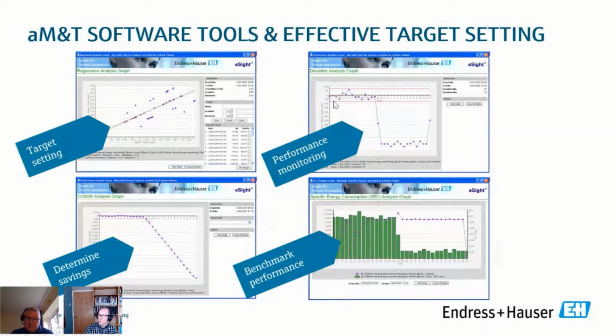Instead of it being nice and flat where we're operating within limits, things start to change slightly, and we see a deviation from that straight line. This tells us, as a condition monitor, that something's changed. It happens to be the same data here—this is an economiser added to a boiler, and we can see a small step change in the efficiency. This adds up those incremental savings over time, so we can see after a certain period what the saving is. This is a good way of predicting and projecting savings using these tools.